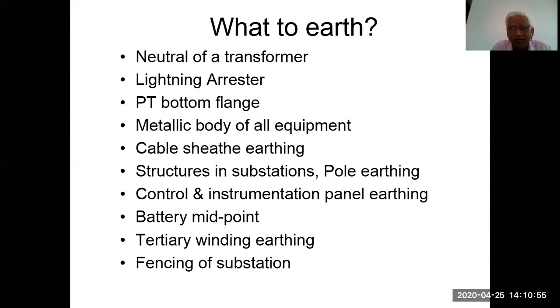Now, what is it that we should earth? What is it that we should not earth? What are all the types of earthing? You can see here, the neutral of the transformer, we earth it. Lightning arrestor, one point is connected to the phase, the ground point is connected. The bottom flange, we call it the bottom flange, is connected to the earth. Metallic body of all the equipment. In the first three, one side there is a supply. Now, metallic body means there is no supply, it is containing a supply inside, but the body has to be earthed. Cable sheathing is earthed, structures in substation, pole earthing is done, and control and instrumentation panel earthing is done.